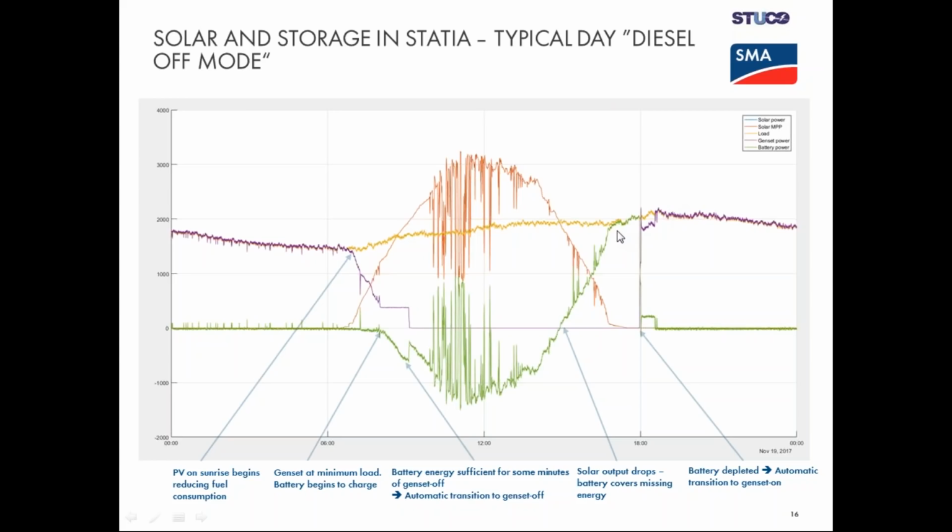So the whole system or the load is provided only by battery power, until the fuel save controller gives the command to switch back on the generators. This happens in basically seconds, minutes, very fast. And we see that we still have a little bit of buffer in the batteries, and we're discharging a bit more energy in parallel to the generator. That's a typical day now. Here it's the 19th of November, and since then, it looks more or less the same each day.